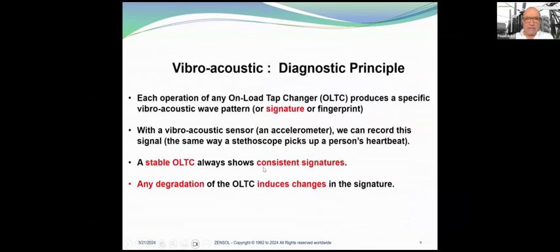What is the diagnostic principle? Each operation of any OLTC produces a specific vibroacoustic wave pattern, which we call a signature or a fingerprint. With a vibroacoustic sensor, which is an accelerometer, we can record this signal exactly the same way a stethoscope picks up a person's heartbeat. And the fact is simple: a stable OLTC always shows consistent signatures. Any degradation of the OLTC induces changes in the signature.